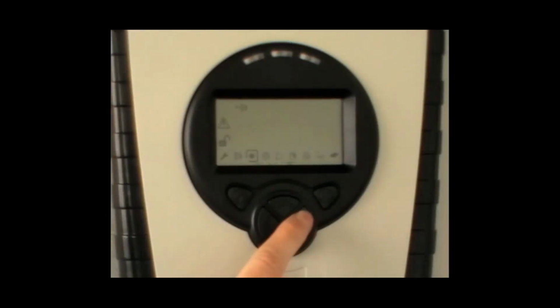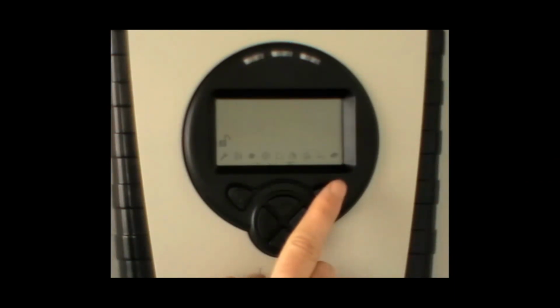Select the Fire Test icon in the Engineering menu. Press Tick twice. The system reports a fire to the Fire panel. Press Cross button to stop the fire test and return to the Engineering menu.